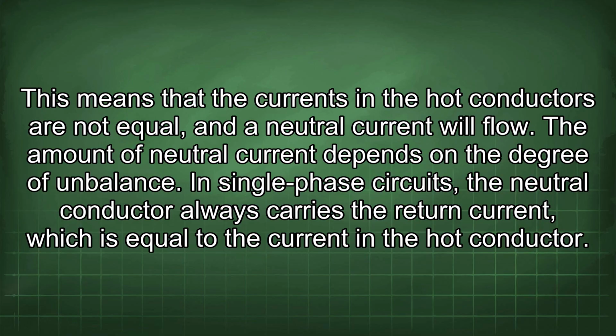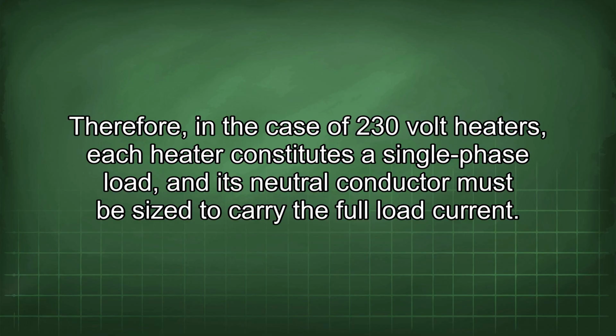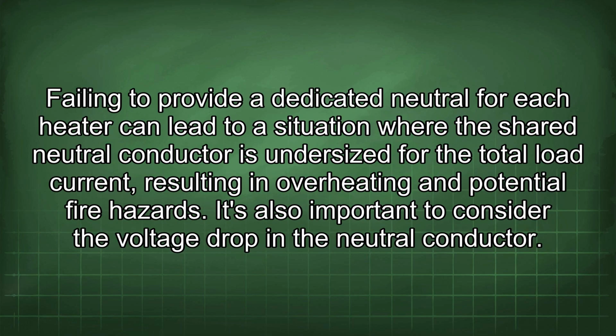In single-phase circuits, the neutral conductor always carries the return current, which is equal to the current in the hot conductor. Therefore, in the case of 230-volt heaters, each heater constitutes a single-phase load, and its neutral conductor must be sized to carry the full load current. Failing to provide a dedicated neutral for each heater can lead to a situation where the shared neutral conductor is undersized for the total load current, resulting in overheating and potential fire hazards.